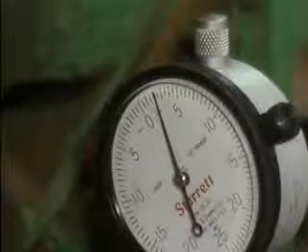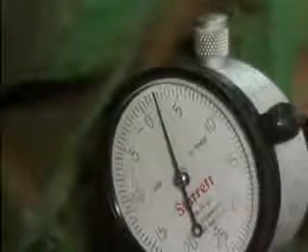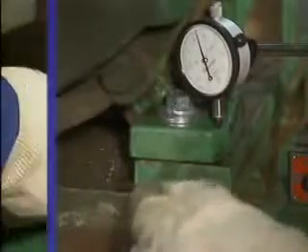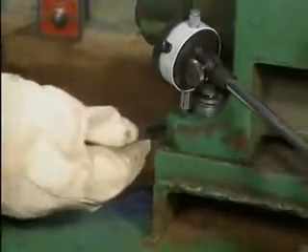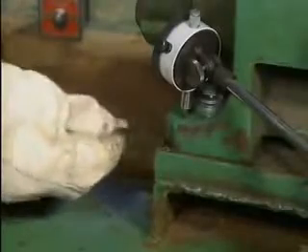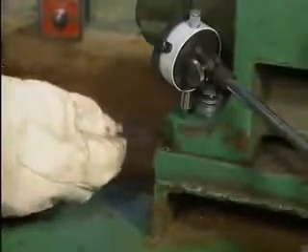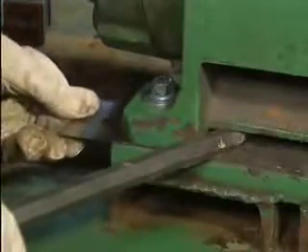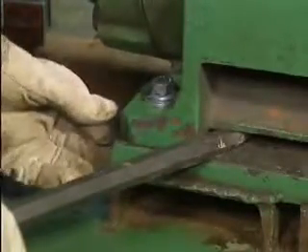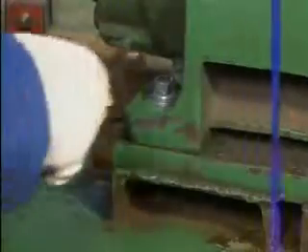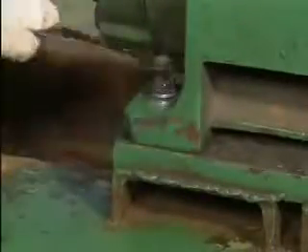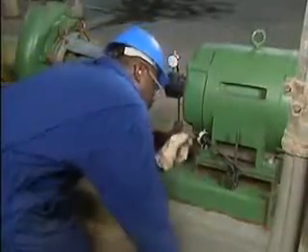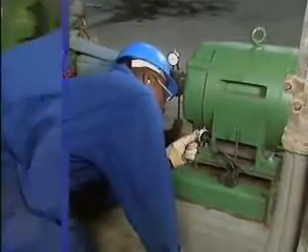Whenever a dial indicator reading indicates that a soft foot exists, it's a good idea to insert a feeler gauge under the foot to check the gap. If the feeler gauge fits evenly underneath the foot, then the foot is fairly parallel to the base. If the foot is fairly parallel to the base, shims of the same thickness as the gap should be installed to correct the soft foot. Then the hold-down bolt should be retightened. And the procedure should be repeated to verify that the soft foot condition has been corrected.